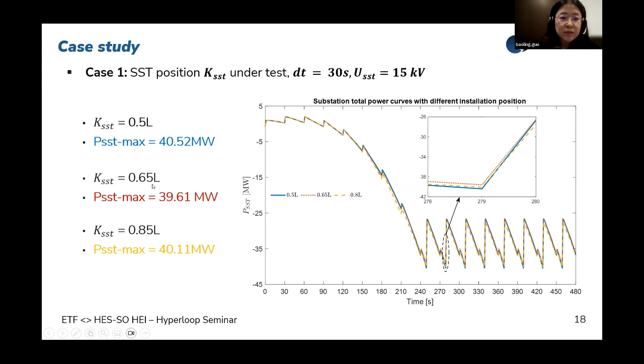And another case study we do is test for the voltage level of the substation. We keep 9 kilovolt and 15 kilovolt for the 2 tests. We can see if we choose the 9 kilovolt, the maximum voltage drop could arrive around 18%, which has not passed the standard we defined, 10%. And for this one, if we choose 15 kilovolt, the maximum voltage drop arrives around 5.8%.